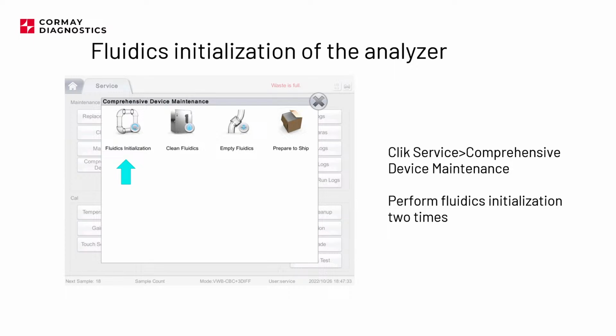And since the analyzer is new, you just removed it from the box. It's possible that some air bubbles are still trapped in the tubes, and you need to make some additional fluidic initialization in order to recover the device from that state. But in most cases, when everything is connected, I mean all the tubes and all reagents, the device should make the initialization by itself. The first one should be done automatically. But just in case, you can use this option.